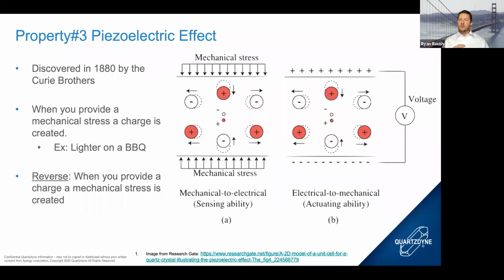And then what we're doing, we're measuring that movement. We're recording that frequency. And when we pressurize our crystal, that frequency shifts. And we look at that difference to the pressure crystal versus a reference crystal. And that's how we're able to determine with such accuracy what the pressure is. But it all happens due to the magic of the piezoelectric effect. Without that, we wouldn't be able to determine with such accuracy what the pressure is downhole.